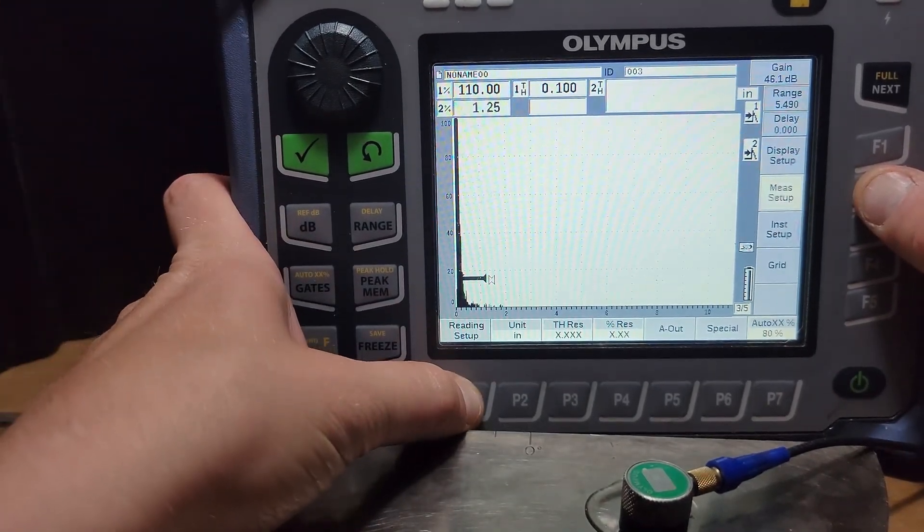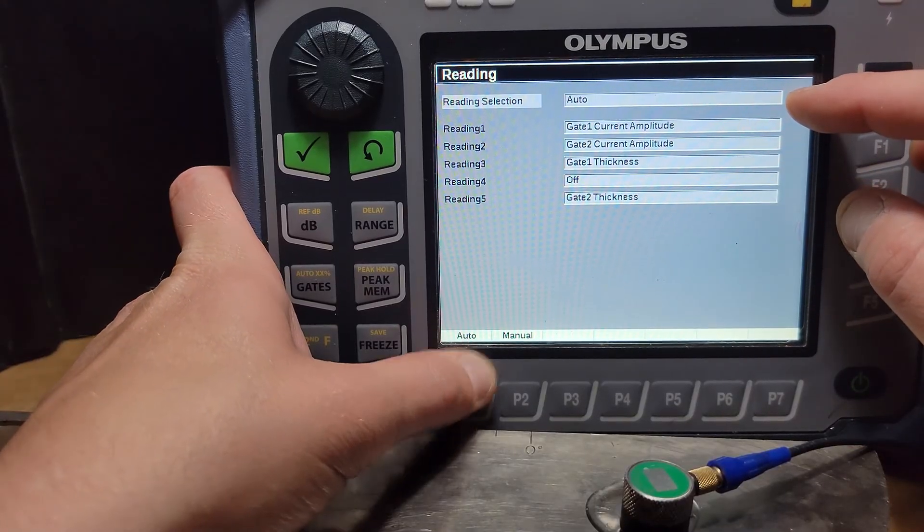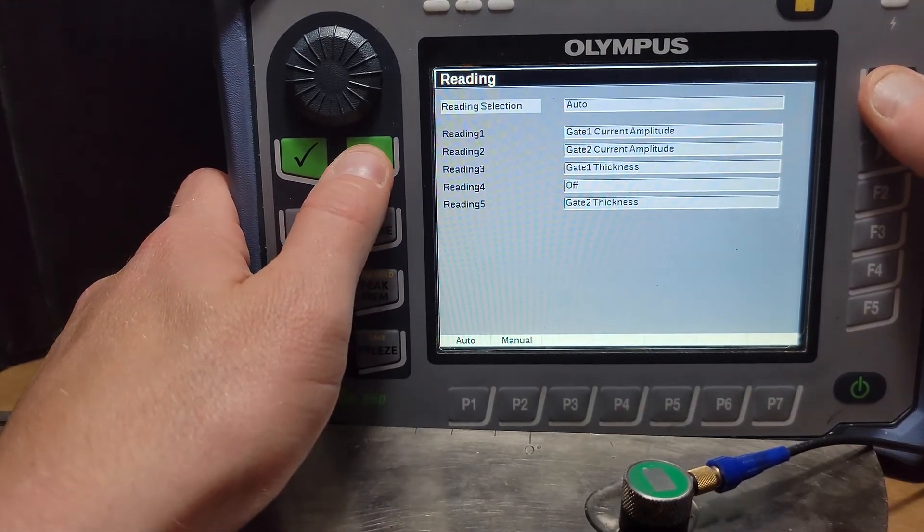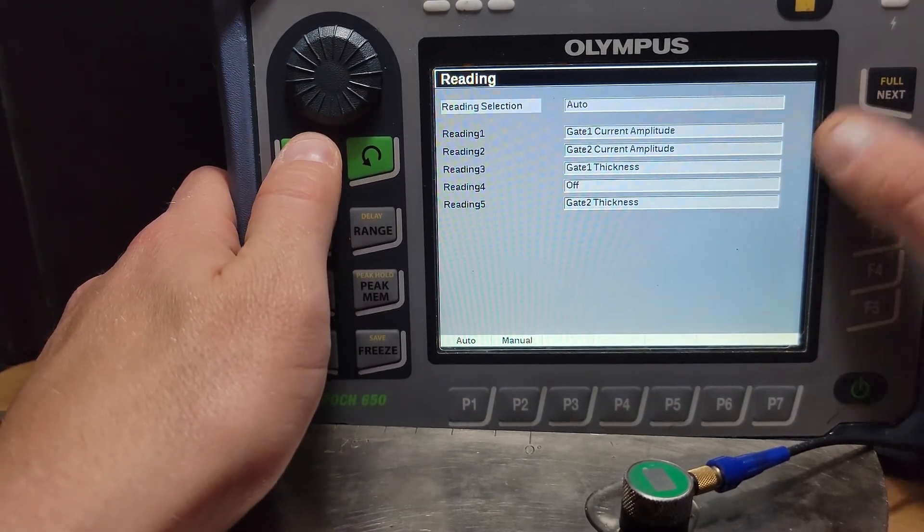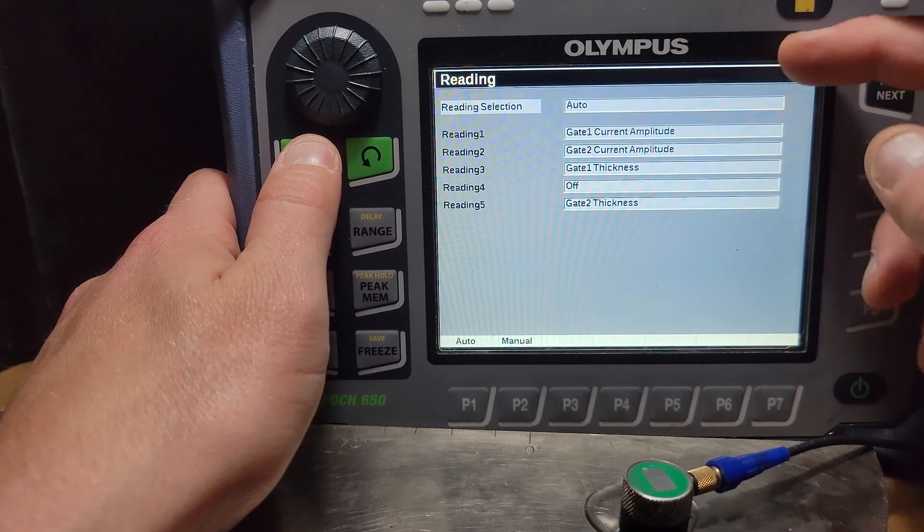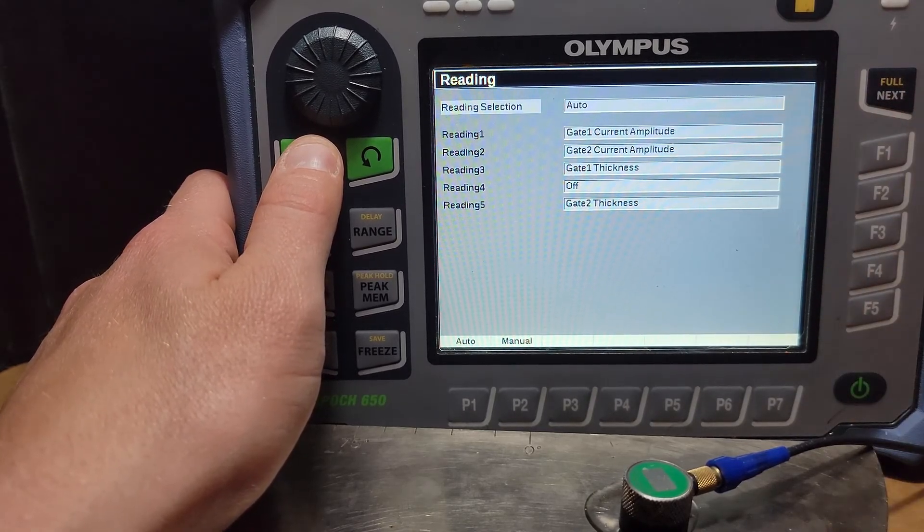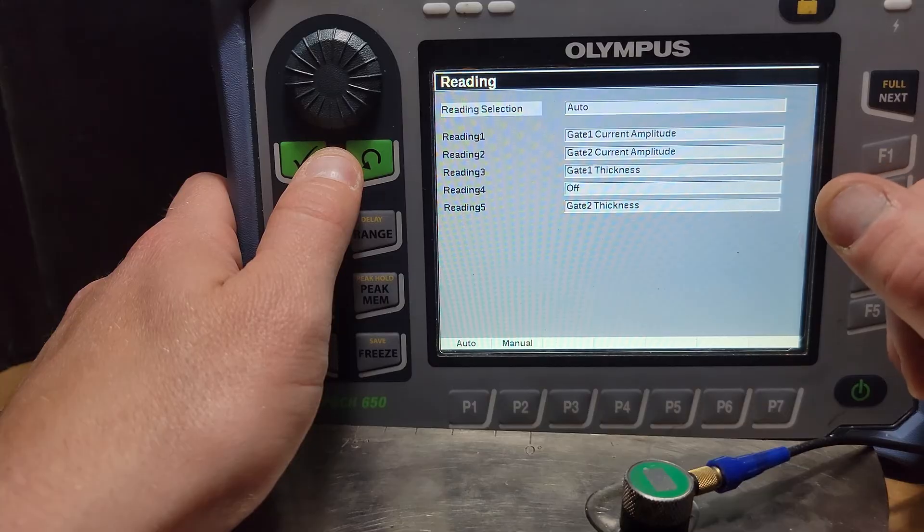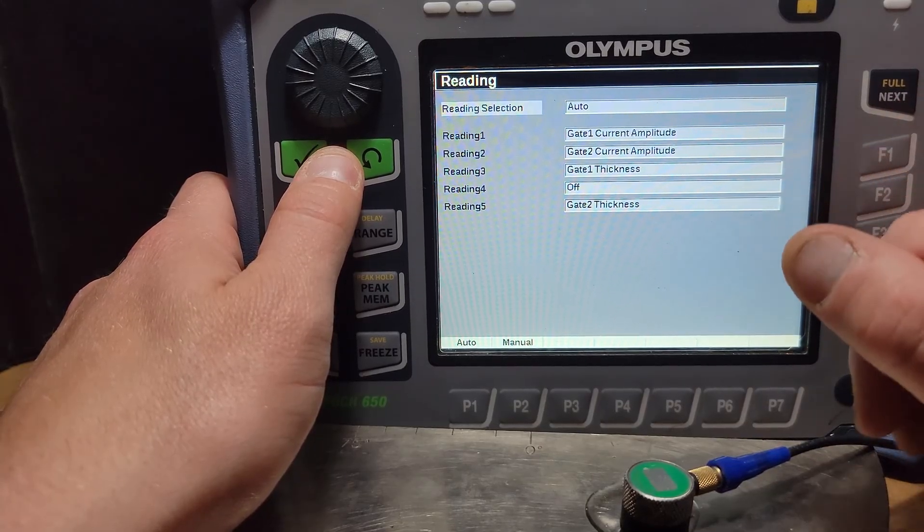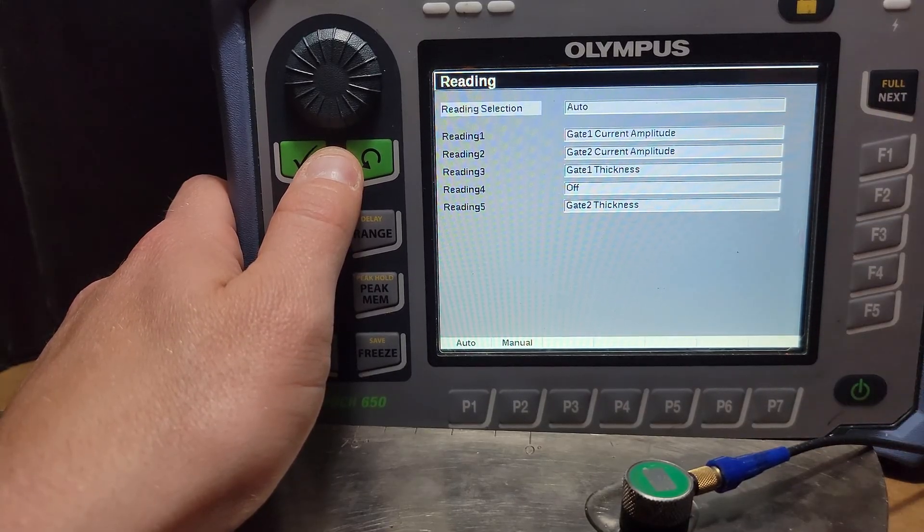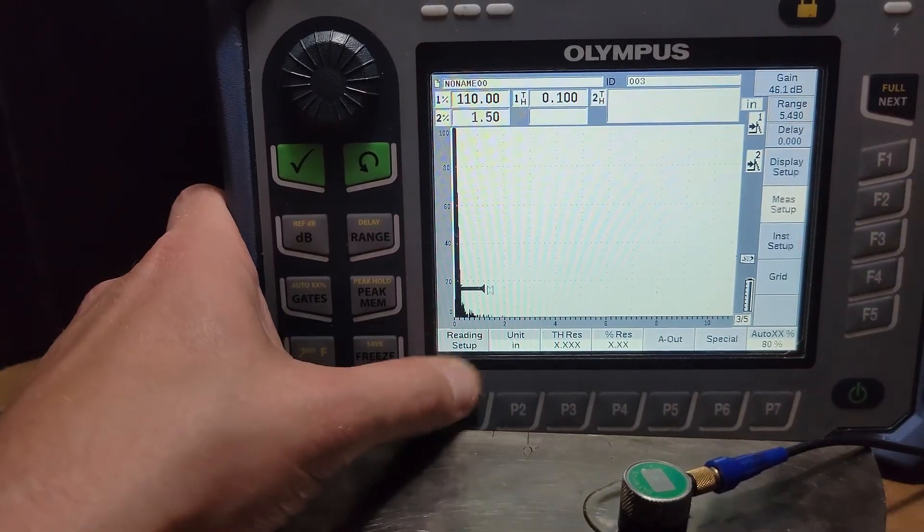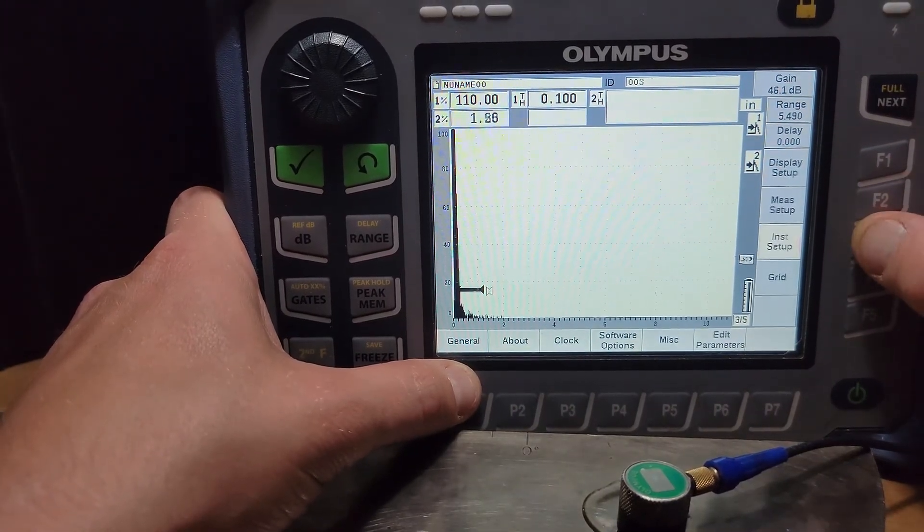If we go into reading setup I've got it set to auto right now but we can actually go in and change those values to measure, let's say we wanted to do gate one minus gate two, or if we wanted to do gate one depth or gate one projected distance across the surface, all those are housed inside of that measure setup.